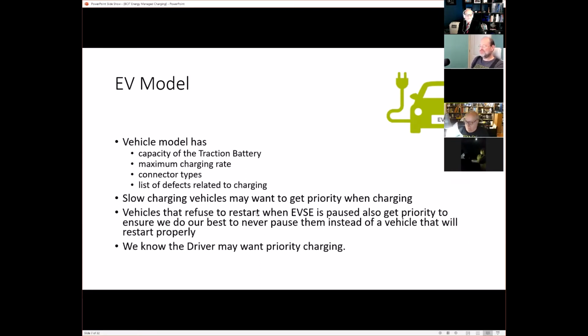As we went through all this, we looked at it and talked to a bunch of different people trying to do this. The way they tried to do it seemed really convoluted to me, meaning they'd say these 2 chargers have a limit of 5 kilowatts together, these other ones have 5 kilowatts, and all together they have 7 kilowatts. The bigger it got, the more opportunity there was for someone to forget one of the settings and groupings, which would cause failures because it got really complicated very quickly to manage.